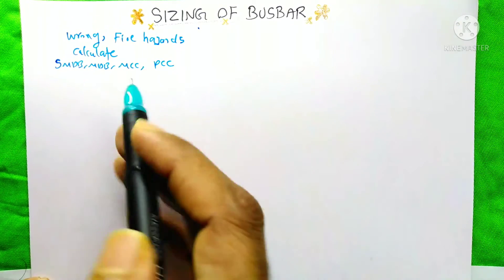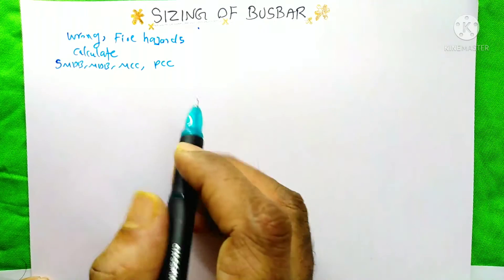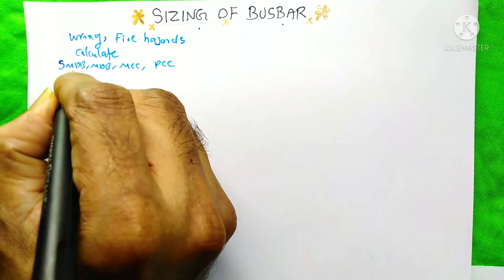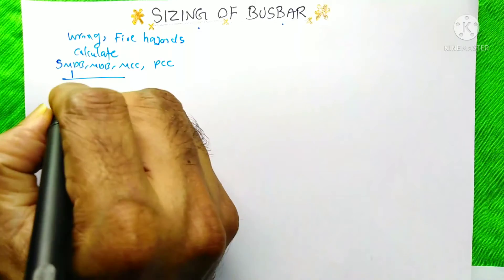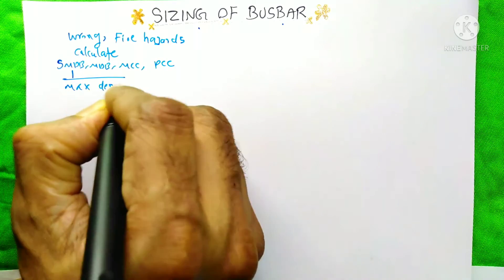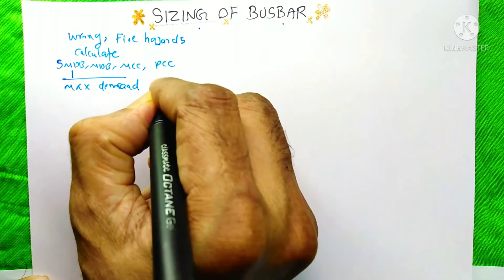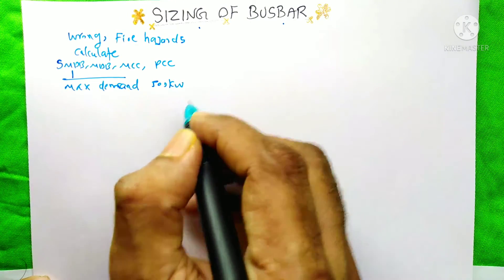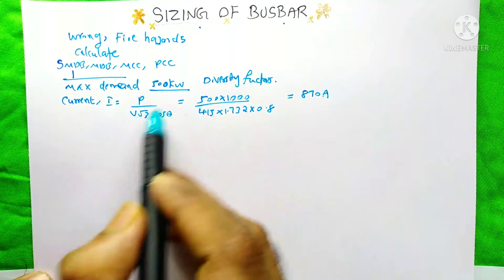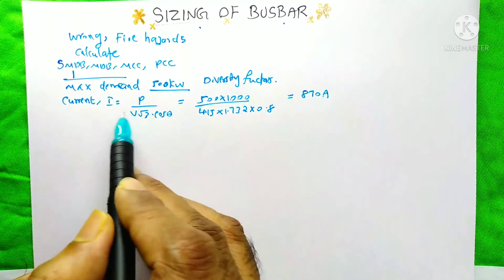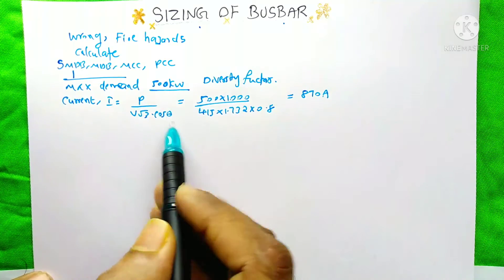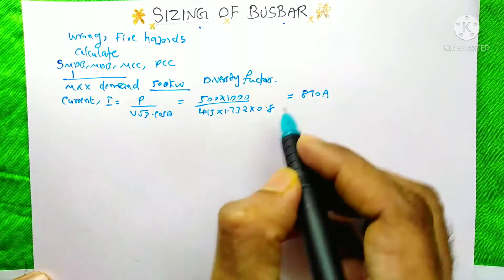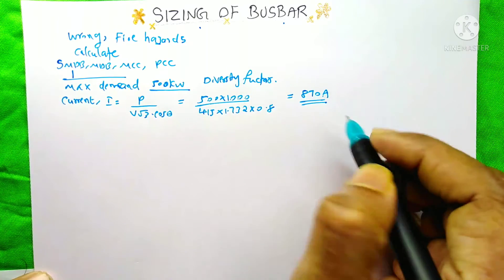For example SMDB, MDB, MCC, PCC — whatever the panel, we do the same calculation for the bus bars. Suppose I am going to calculate the bus bar for this SMDB. I am taking the maximum demand of this SMDB as 500 kilowatt. The current is calculated using I = P / (V × √3 × cos θ), so 500×1000 / (415 × √3 × 0.8) = 870 amps.